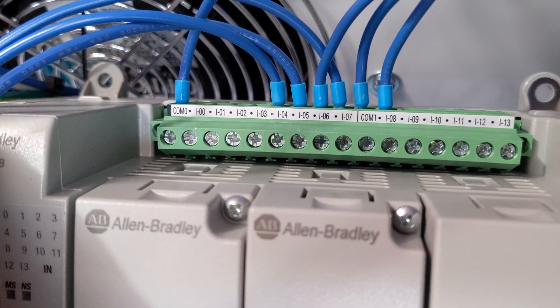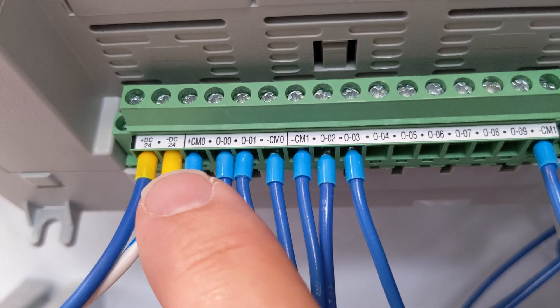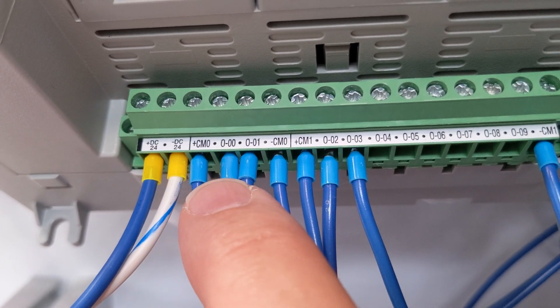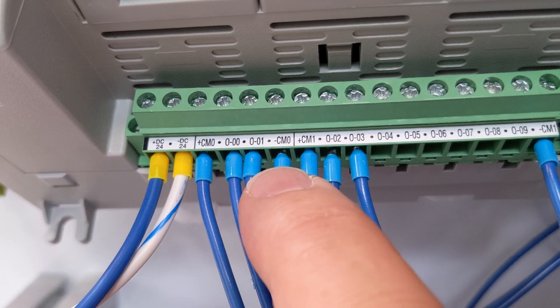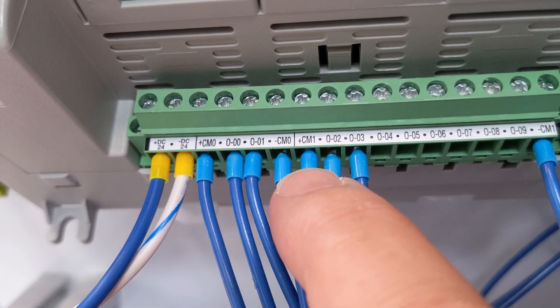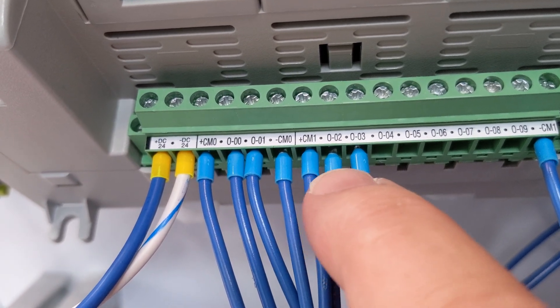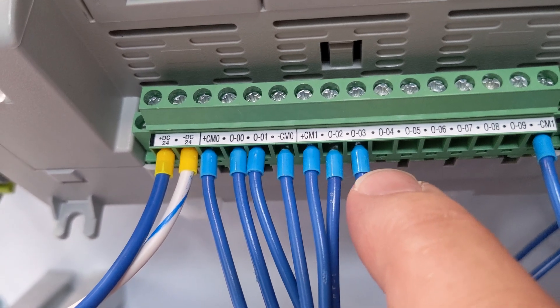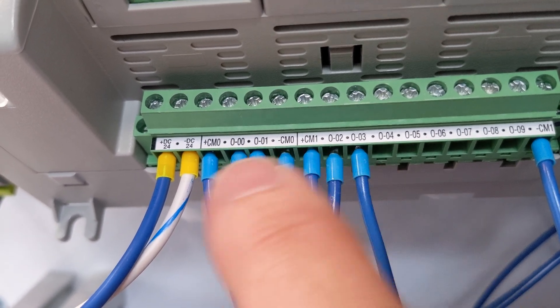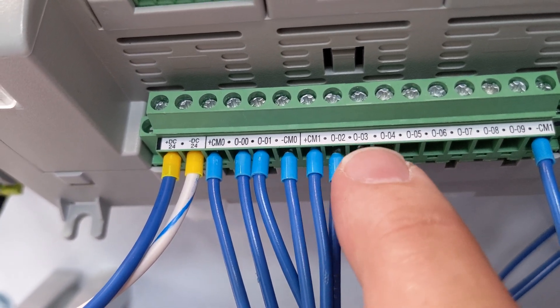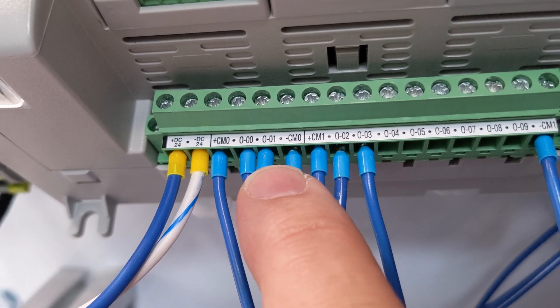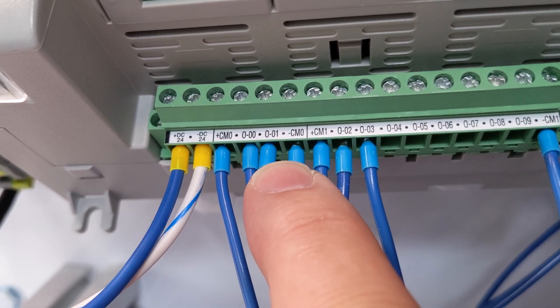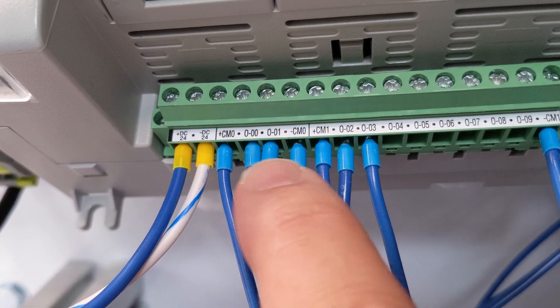And on the bottom side, you should have wires on plus COM0, output 0, output 1, minus COM0, plus COM1, output 2, output 3, and minus COM1. Now, this is the one that trips people up. The minus on both of these go to the 0 V. They go to that right set of terminal blocks.